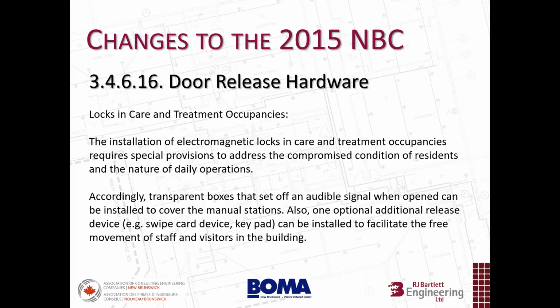One of the tools that can be used here to limit and avoid these sensitive occupants from overriding these electromagnetic locks and getting out is to use transparent boxes that set off an audible alarm when opened. They can be installed to cover the manual stations that will release these electromagnetic locks. Also, there's one additional optional release device: we can have keypads and swipe cards to facilitate the free movement of staff and visitors in the building.